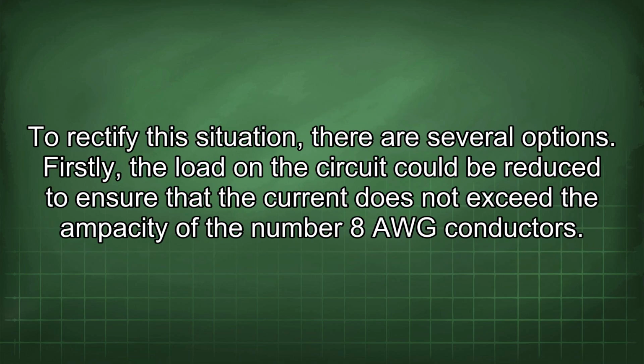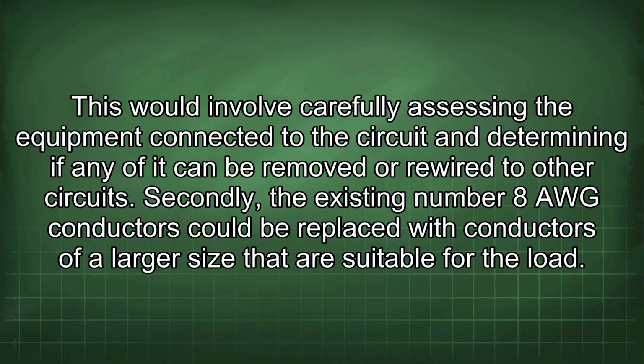To rectify this situation, there are several options. Firstly, the load on the circuit could be reduced to ensure that the current does not exceed the ampacity of the number 8 AWG conductors. This would involve carefully assessing the equipment connected to the circuit and determining if any of it can be removed or rewired to other circuits.